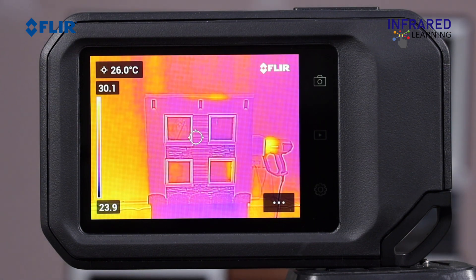The FLIR C5 is a fixed-focus camera, so adjusting the focus is not necessary. However, there is a minimum focus range of around 4 inches. For regular predictive maintenance or building inspections, this is a distance you're probably never going to be operating at with this camera, and it is also within the safe approach distance when inspecting electrical equipment — so it's not a concern, but it's something you should be aware of.